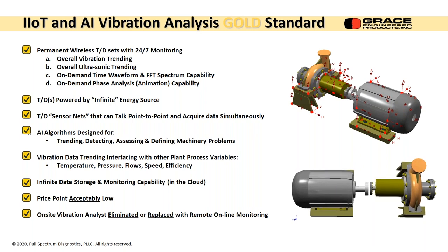So this is something I've done the last couple of years, and I continue to look at where the technology is going with a wireless transducer, in cloud, data storage, all that type of stuff. The gold standard, the thing that everybody's looking for, is the permanent wireless transducers, 24/7 monitoring that can do a lot of things. And the four things that are of main interest right now are overall vibration trending, which is just an energy level response of the machine, and overall ultrasonic trending, which is a filtered high frequency failure mode for rolling element bearings.